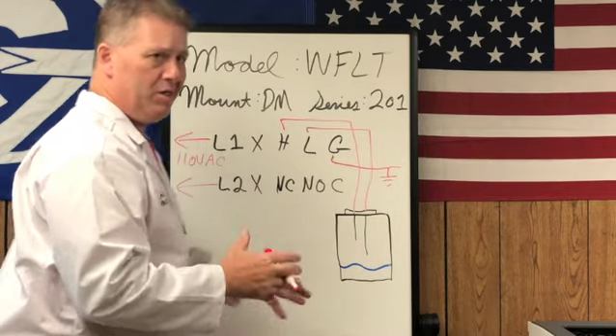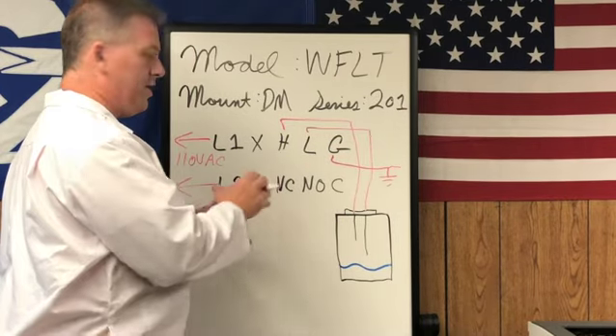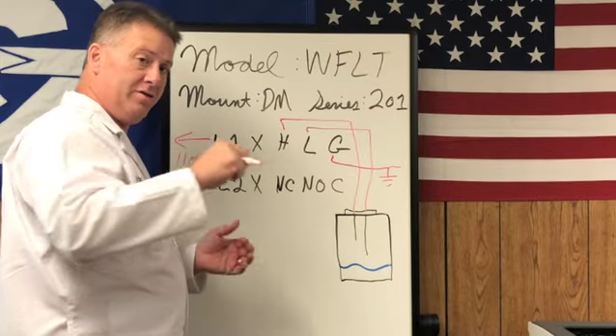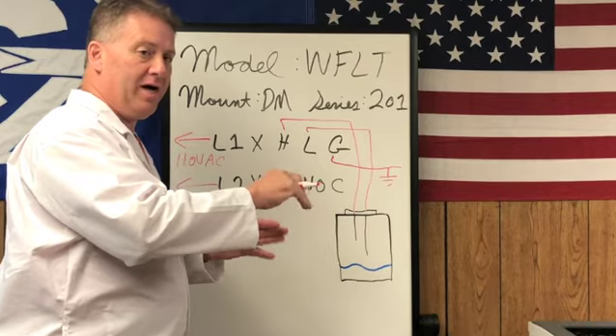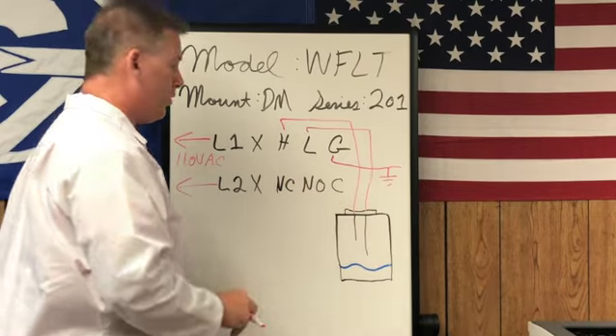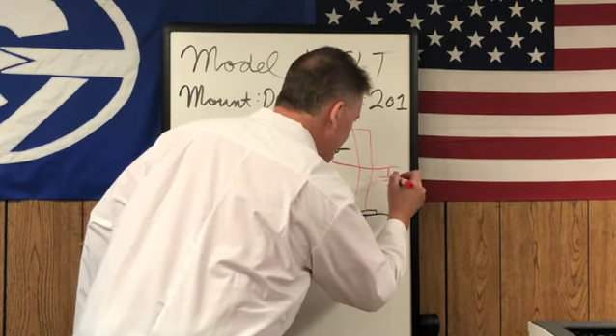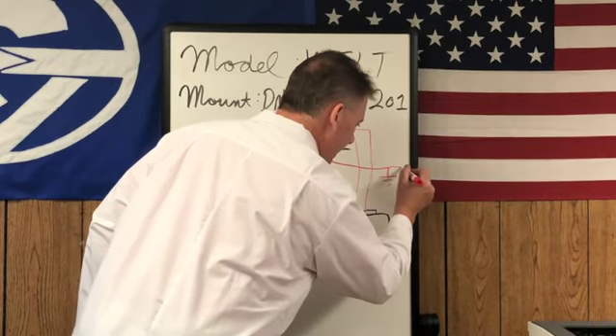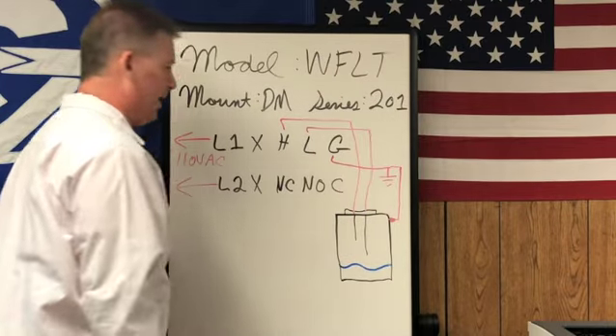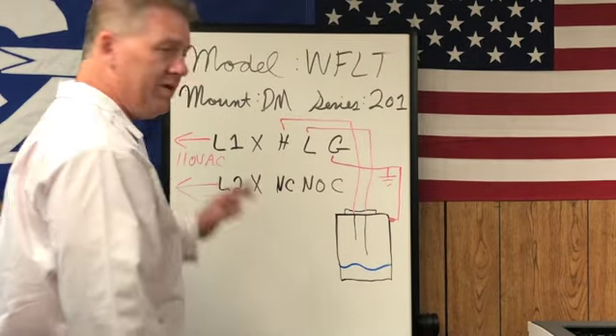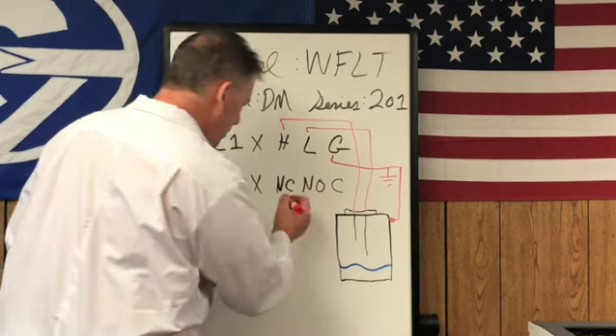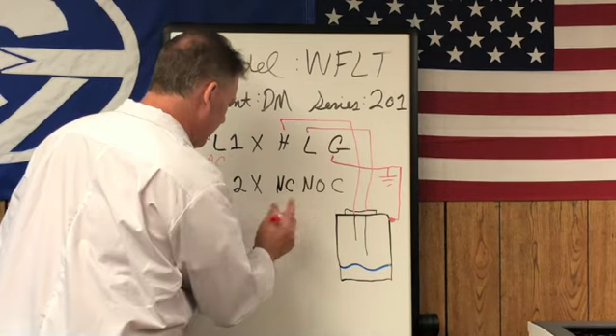So if you have a panel or a cabinet that you're putting this DIN rail mount in, and it's a metal cabinet with a good ground, you're in good shape there. But for this one, we're going to use any good earth ground. You can also bring it to the metal tank if you have a metal tank. So, filling operation. Normally closed, this is the side we're going to be going with.